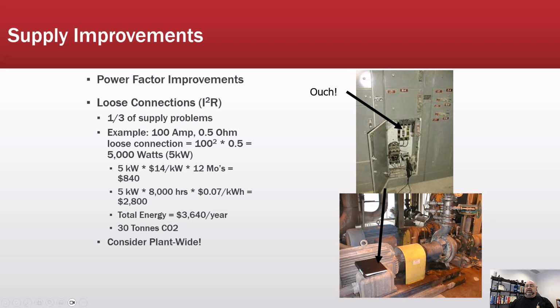Now, is that too ridiculous? Well, we've seen a few something like this. As a matter of fact, we've seen loose connections or even other things that have generated single-phase conditions in a machine that will run along the same type of lines, because the drop goes across where it is. In this case, I've got a slow blow motor fuse, I've got a fast blow fuse, and then I've got a lighting fuse here. The lighting fuse, when we were testing, because we got a really odd reading when we were doing our energy analysis, that was single phasing that 100 horsepower motor.